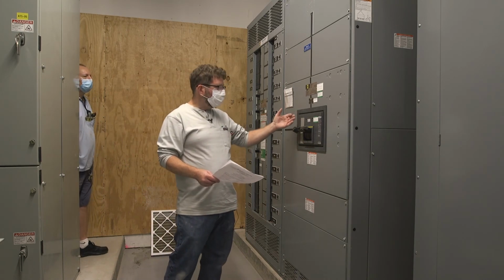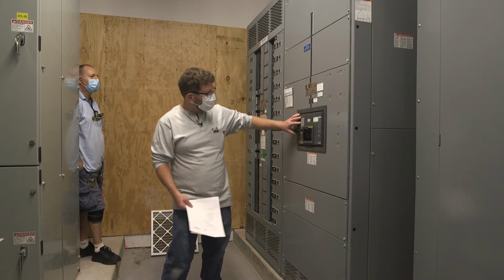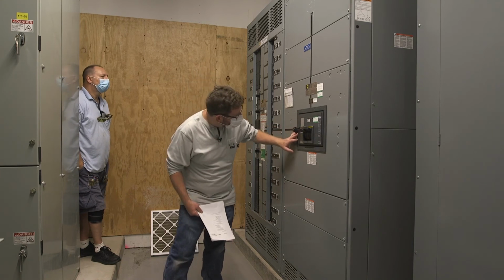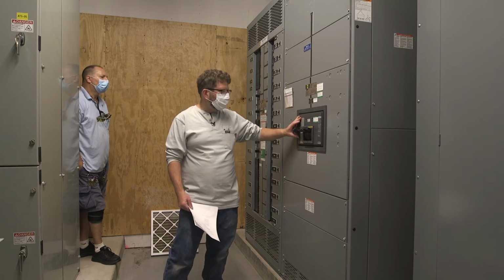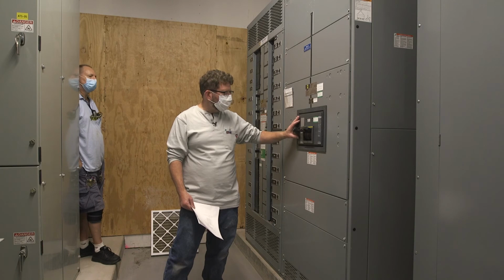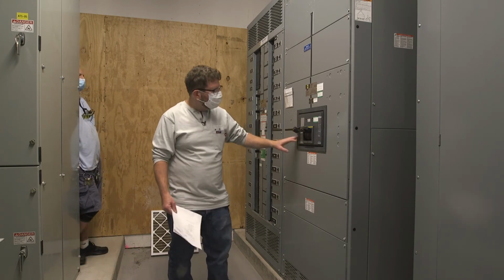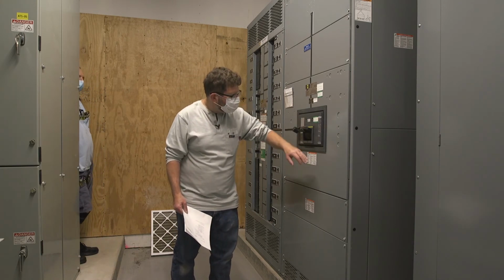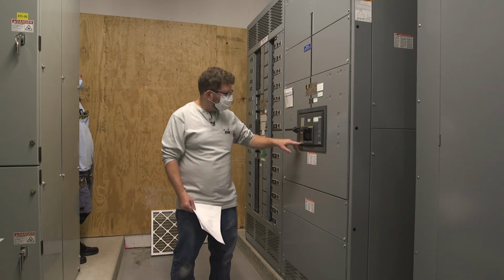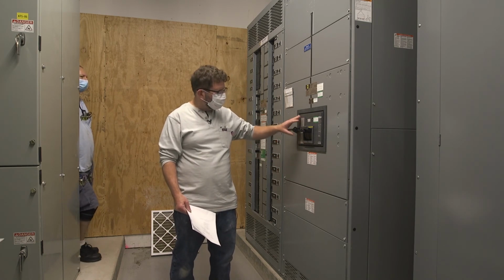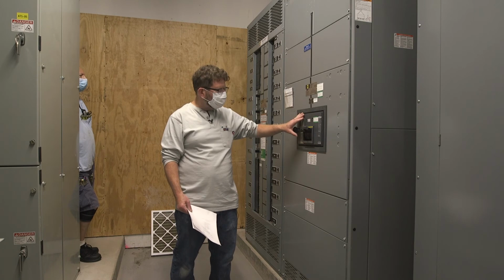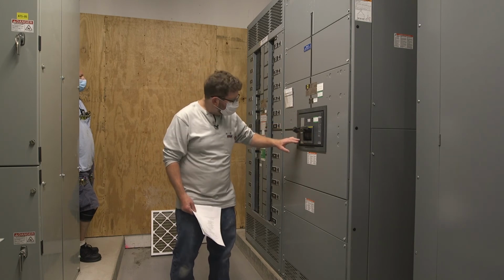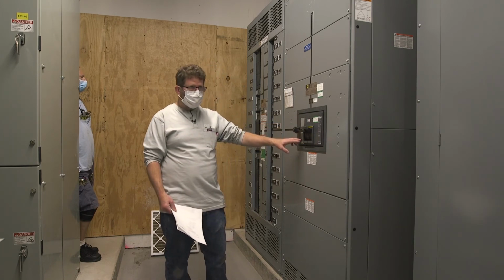Here you have a main breaker. This has another trip unit. It's not nearly as functional even as a fire pump breaker. It's an R-frame 1600 amp breaker, 1600 amp sensor plug. That long time protection is not adjustable on this. The only thing that's adjustable is you have an instantaneous setting here.